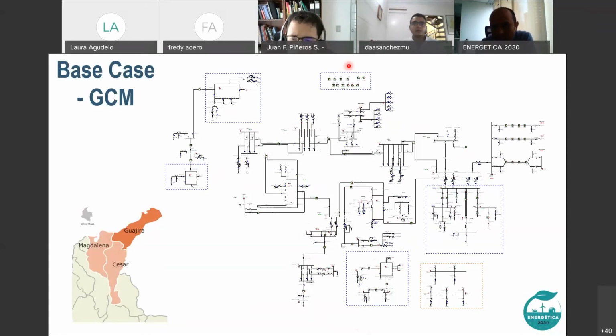David, and I think it's important as well to say, for protection purposes, an exact model is the model that gives you the behavior of the currents the inverter generates, or the voltage at the point of interconnection. This is very important because there are two ranges of time that matter: the transitions when the fault is happening, and the steady state of the fault, and how the inverter is putting out the currents or the voltage at the same time. Both matter, and you have to get this right, because there are several kinds of black box models, but sometimes they are not accurate for the transition of the impedance, for example, because of how the inverter is recognizing the fault, going off temporarily and restarting to inject the dynamic reactive current support.